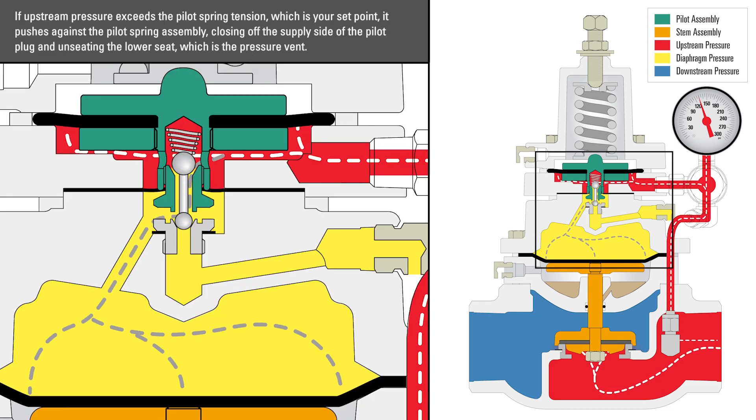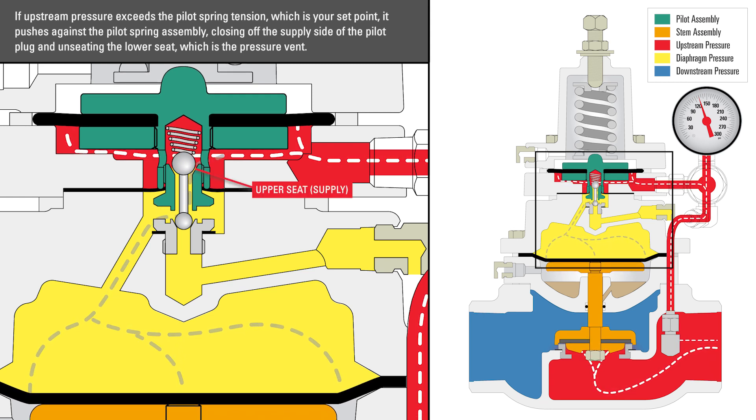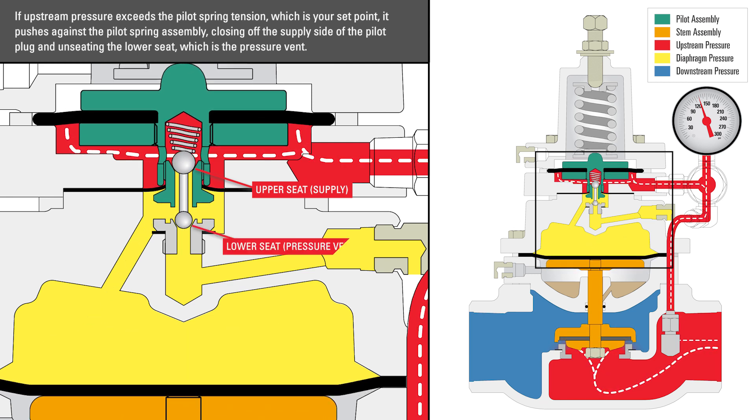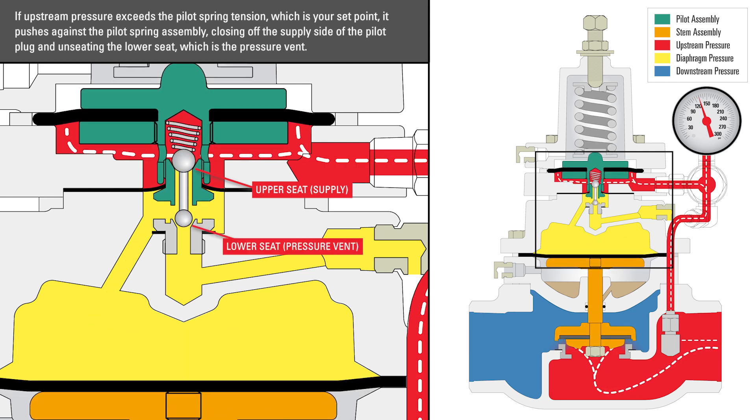If upstream pressure exceeds the pilot spring tension, which is your set point, it pushes against the pilot spring assembly, closing off the supply side of the pilot plug and unseating the lower seat, which is the pressure vent.